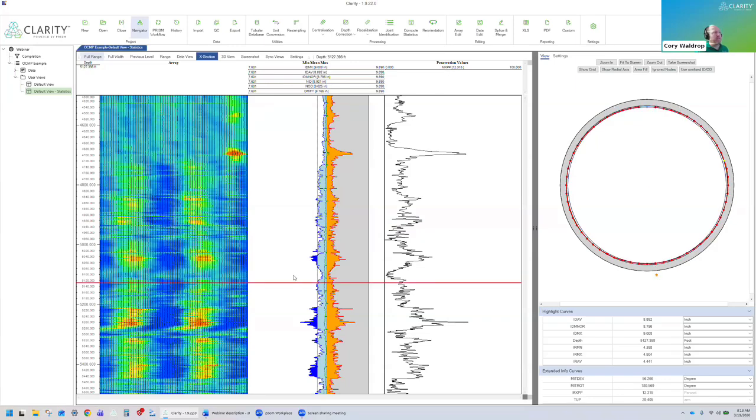This data set has already been fully processed. And you can see anytime this maximum diameter increases, your maximum penetration increases. It's a direct correlation. And that's a problem because we've already determined that this is just oval pipe. It's not true metal loss. So we would be reporting drastically exaggerated values.